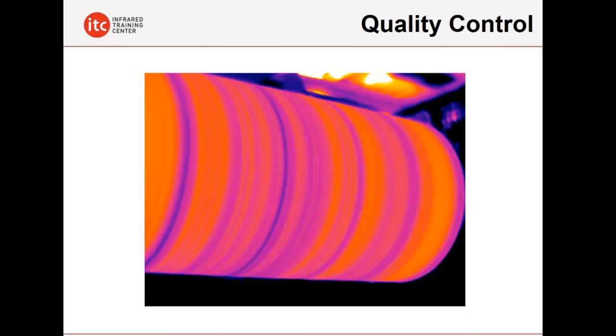In the paper industry, this could be toilet paper, or paper towels, or newspaper, printing paper. The darker areas here represent potential moist areas that aren't drying properly. This is something where IR is used in more of a process control situation, where if this was a product that we were manufacturing, that moisture can be detrimental to the quality of that product. IR can then be used to make sure that things like the dryers are functioning correctly, so that we don't have a loss in this situation.